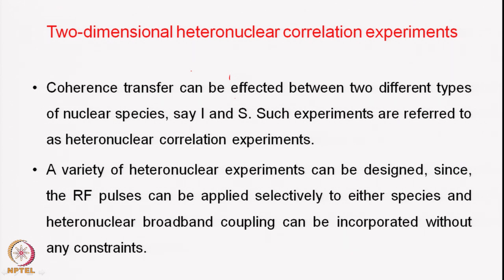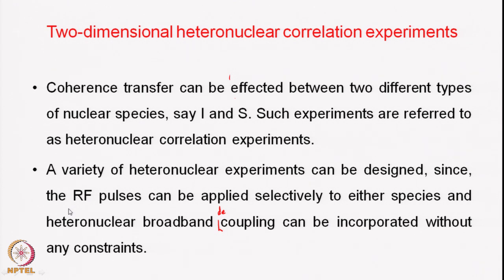You can design a variety of heteronuclear experiments because the RF pulses can be applied selectively to either species. Proton and carbon are very widely separated in terms of frequencies, therefore application of the pulses is not a problem. You can also do heteronuclear broadband decoupling without any constraints. During the indirect detection period or the evolution period where there is no acquisition going on, you can also do various kinds of decoupling tricks.